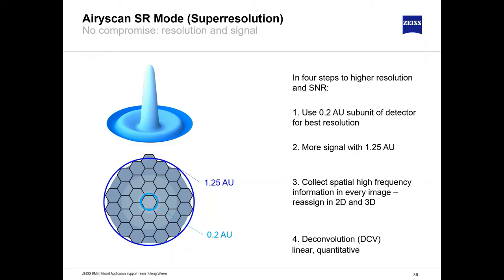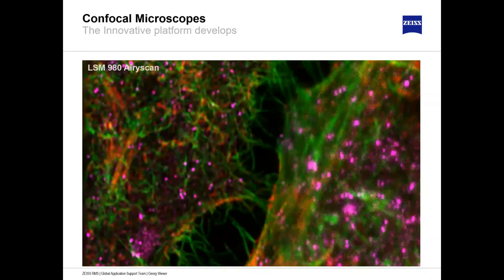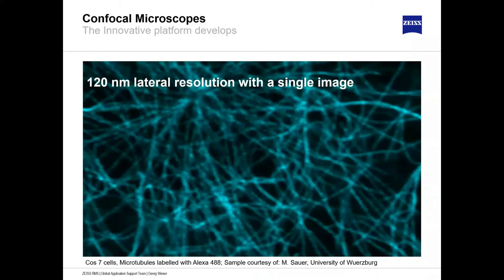Airyscan revolutionized confocal imaging. It increases resolution by a factor of two in all directions — XY and Z — and also increases the signal-to-noise ratio by a factor of four to eight. Sample preparation and labeling stay the same, pushing confocal imaging to the next level in terms of speed, signal-to-noise ratio, and resolution. You can generate very nice quantifiable images with 120 nanometer lateral resolution from a single image.